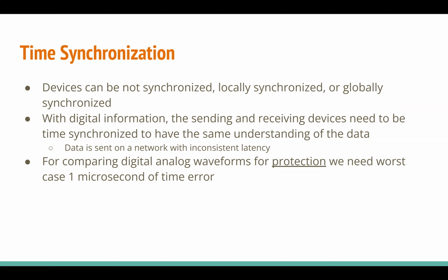The ideal is for everything to be globally synchronized, which means everything has the exact same concept of time. Every device we would possibly want to work with knows it's exactly 12:01 right now. When we have digital information, the devices need to be time synchronized to be able to compare that information. If two devices have a voltage waveform and want to compare them against each other, and one thinks it's a few milliseconds in the future and one thinks it's a few milliseconds in the past, there's going to be an offset. If they then try to calculate something like a differential current, one minus the other, the values aren't going to be correct.